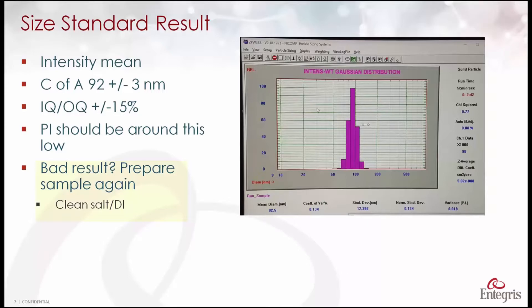The place to first focus your attention is how clean is the diluent, the salt solution or the DI water you used to dilute the sample, or maybe the beaker used to prepare the sample.